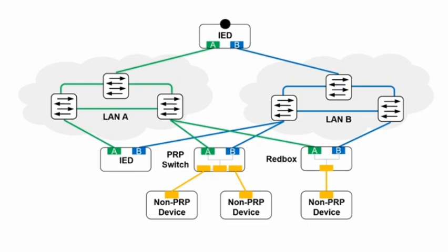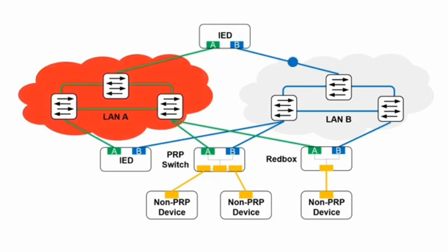Every packet sent by PRP nodes is duplicated. One copy goes through LAN A, while the other goes through LAN B. During normal operation, the receiving side would get both copies but use only the one that came first and discard the one that came later. Creating and discarding duplicates is done using special hardware either in a RedBox or embedded into a device. At any time, we can afford to lose one of the LANs without any packet loss, so the network recovery is seamless.